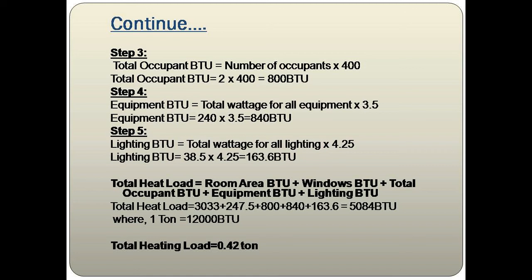Step 4 — Equipment BTU: total wattage for all equipment = 240 W (two computers). 240 × 3.5 = 840 BTU. Step 5 — Lighting BTU: total lighting wattage × 4.25 = 38.5 × 4.25 = 163.6 BTU.